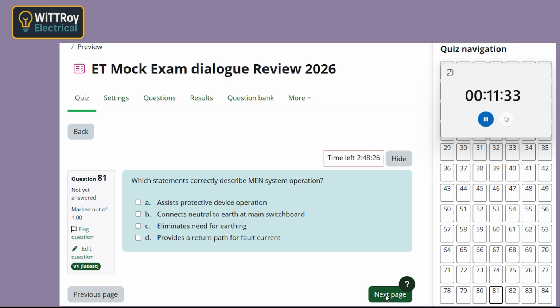Now, the reason for that is to make sure if something goes wrong, fault current has a solid path back. So protection can actually operate. Yep, that's the key. Without that path, faults might not clear properly. So it helps safety. Exactly. And it doesn't mean we don't need earthing anymore. That option is wrong.